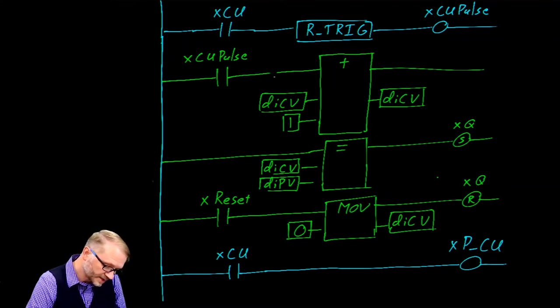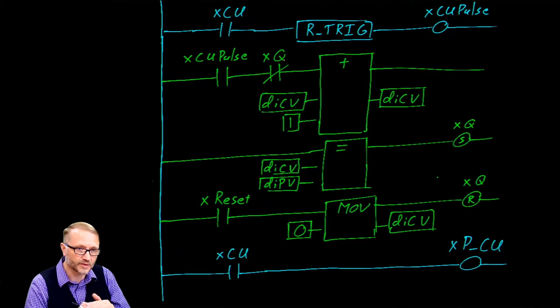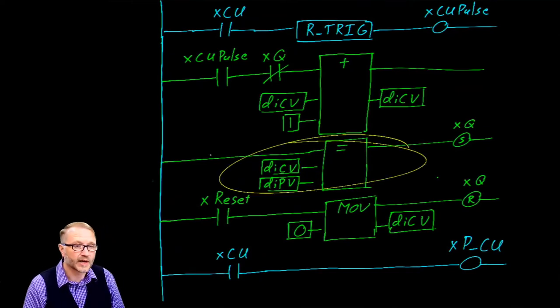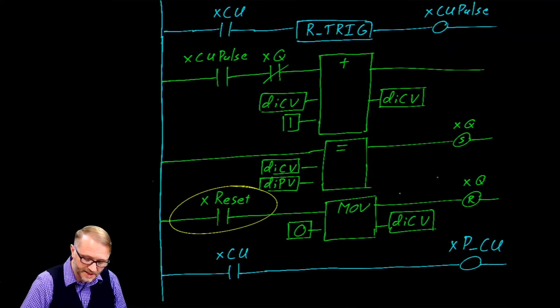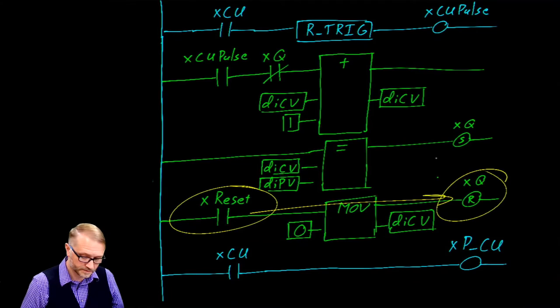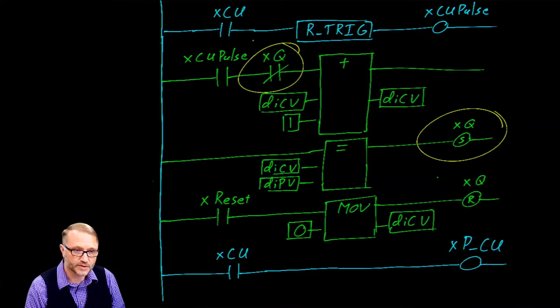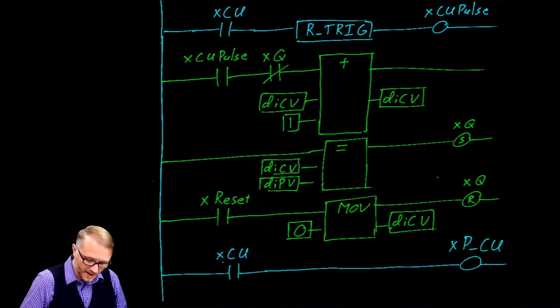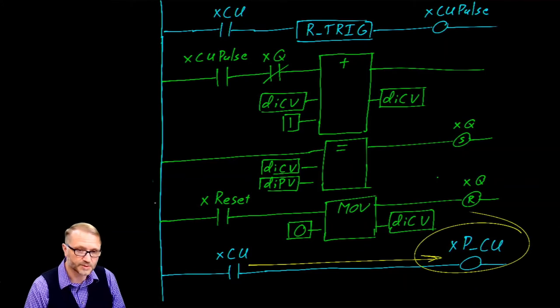We should add one minor change here. We will disable the addition if Q is set, which means it'll count every time there's a pulse until our current value is equal to program value, in which case the counter will stop and halt where it is. We have this test for equality where we're always comparing our current value to our program value. When they are equal, we latch Q. Q will remain latched until reset removes the latch. And this last rung just makes life a little bit easier by taking the value of count up and preserving it as an output called the previous count up.